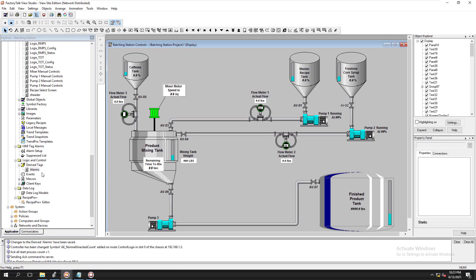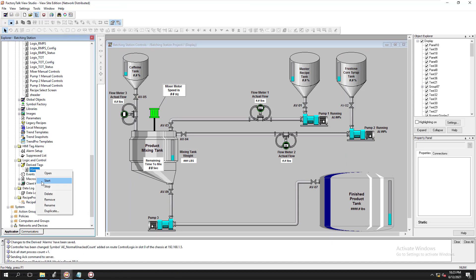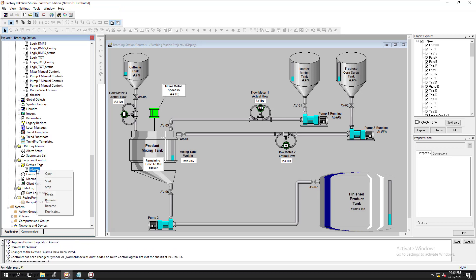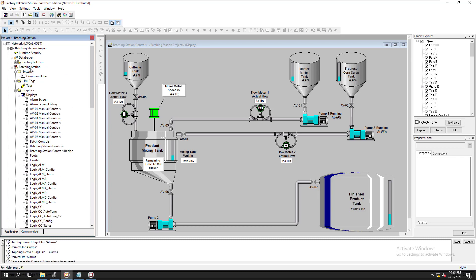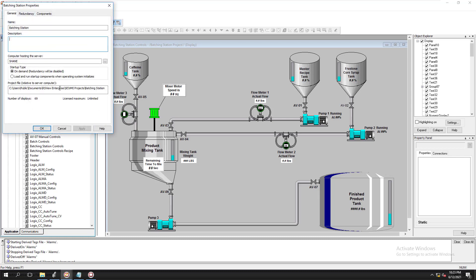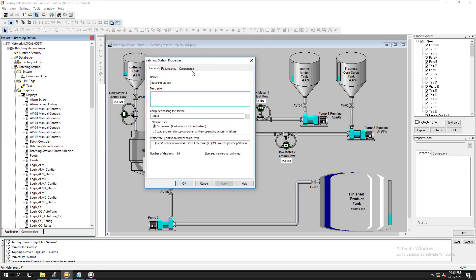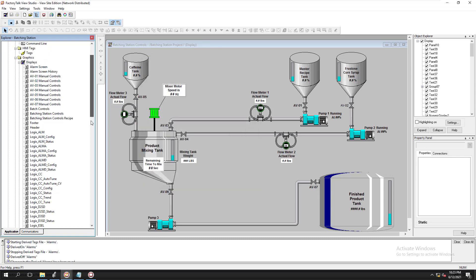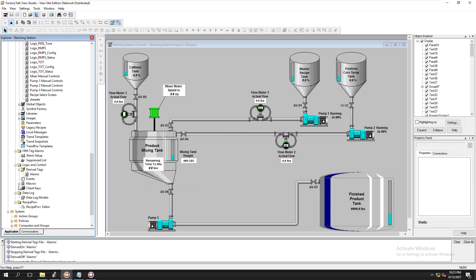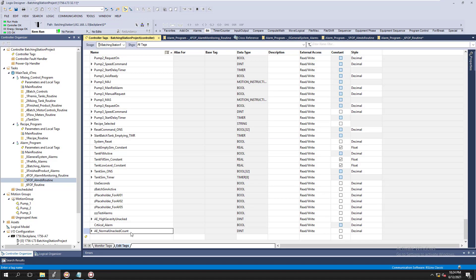Now we've added a new derived tag, so it very well could need to be restarted. We'll stop it and then restart it. Remember, controlling your derived tags — you can come up here to your components in your HMI server and control them from your components when your HMI server is starting and stopping. Or you can control them from a macro, or just do it from derived tags as we just did as a test.